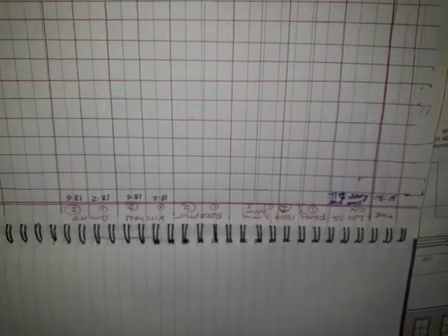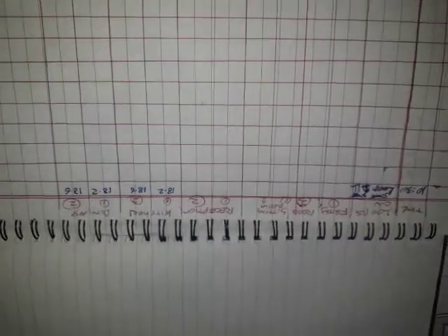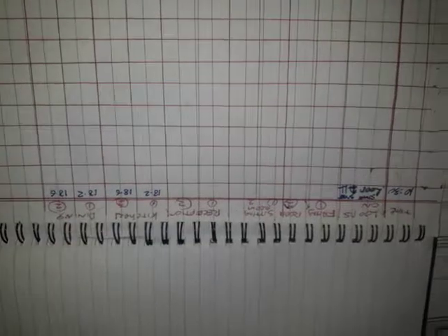It's very important to say that we must start this experiment when the underfloor has been off for at least 7 or 8 hours, and preferably overnight, like 12 hours, to allow the floors to cool. That's quite important. And then when we've allowed them to cool, we turn on loop 1.